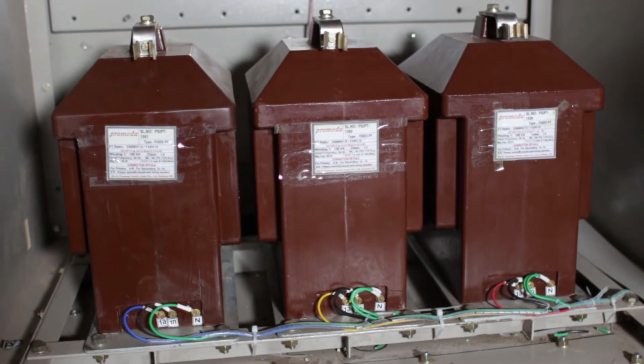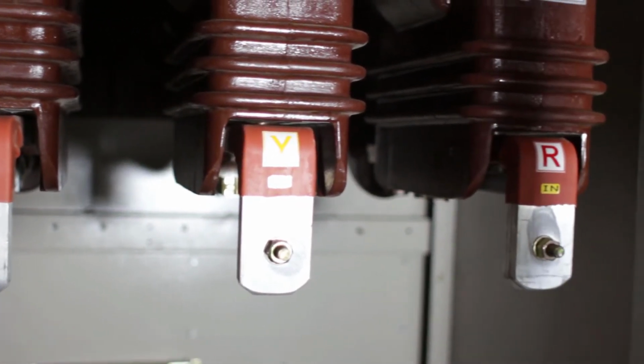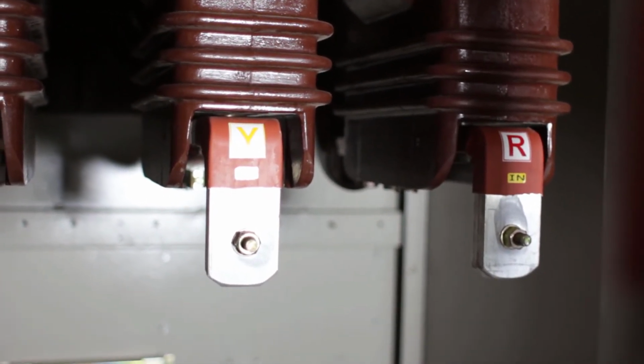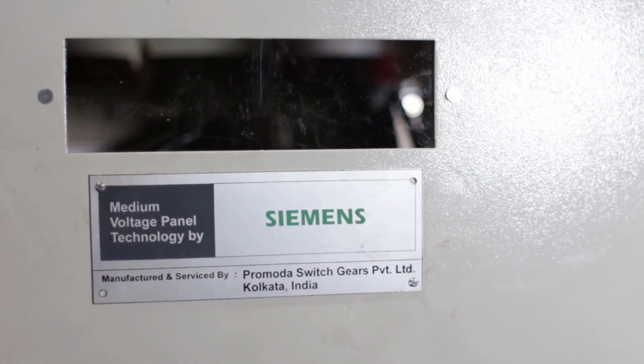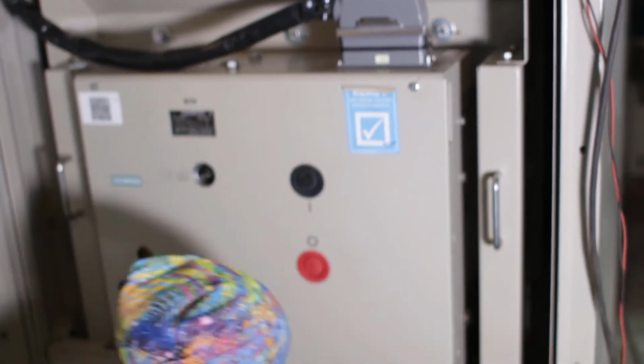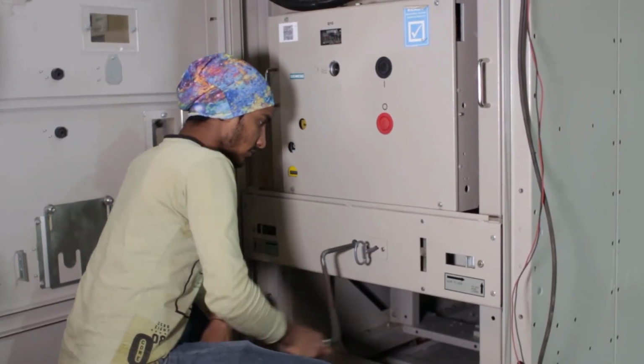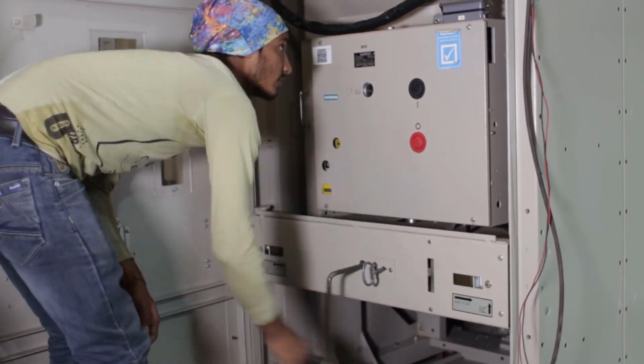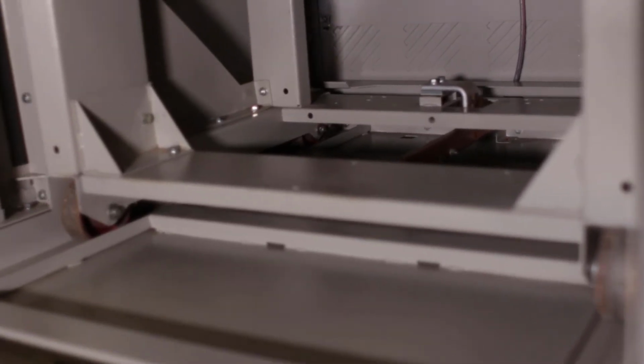Interrupters provided in the VCB are totally restrike free and suitable for rapid auto closing as per duty cycle 0.3 second to 3 minute. It has long maintenance free life, a high switching capability. CTPT are housed in separate compartment which are epoxy cast type and are manufactured in Promoda factory by vacuum impregnation method.